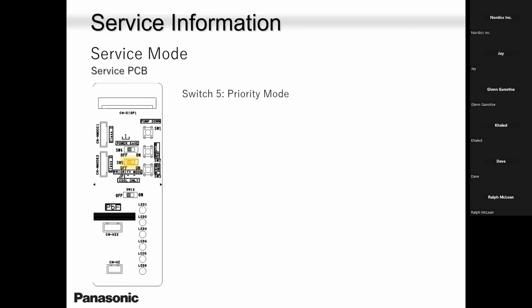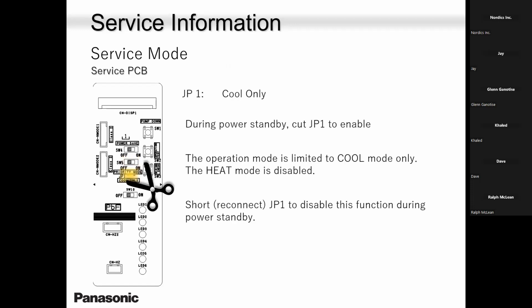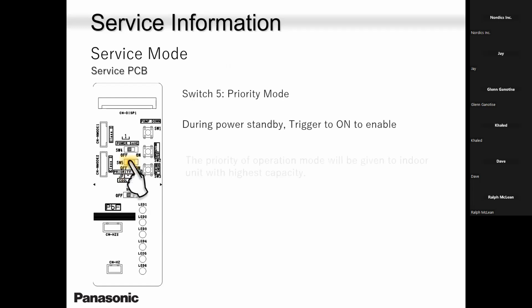Priority mode is given to the indoor unit. Sorry, where is priority mode? Priority mode is given to the indoor unit that you want to be at full capacity. So let's say you have a 12, 15, and a 9. Basically, if you flip that, you're giving full capacity to the 15. But also, if you want to give full capacity to the 12 or 9, you can do that as well. But basically, priority mode is good.